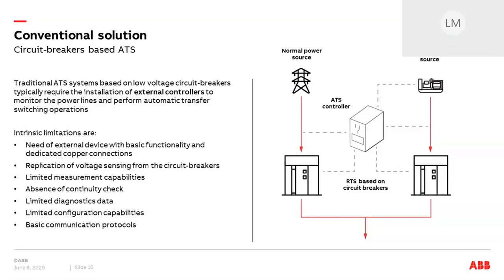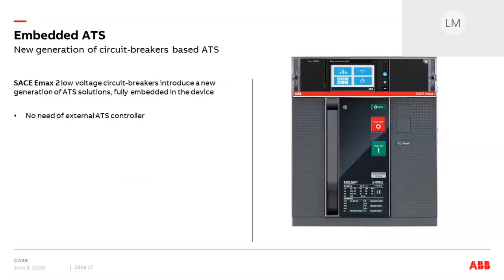So the question is: why not fully exploit the advanced capabilities offered by the ATS circuit breakers? The embedded ATS function is the answer to this technological evolution. ABB Ekip and EMAX2 circuit breakers offer the possibility to fully embed advanced logics in one single device by taking advantage of the most advanced features of the protection trip units — with no need of any external controllers.